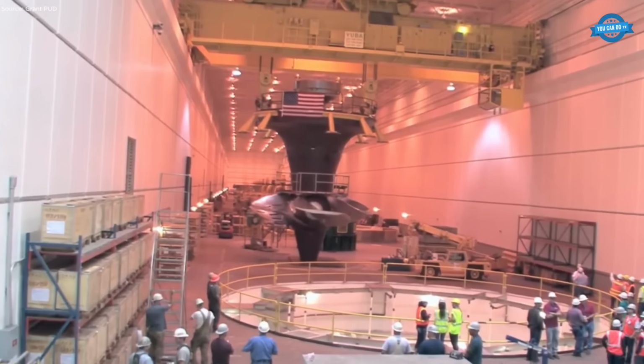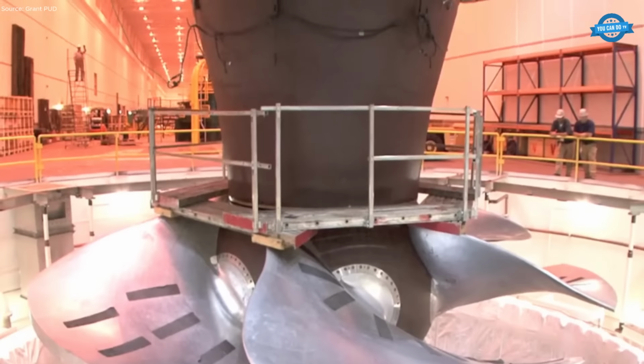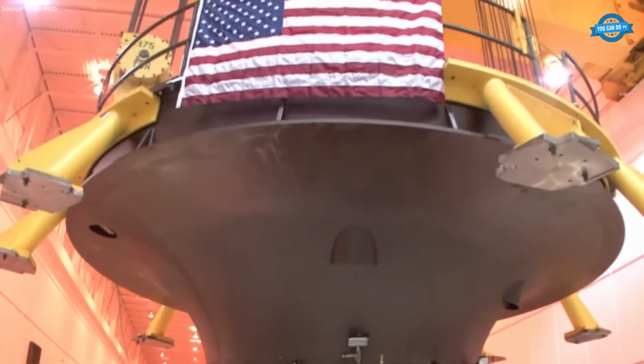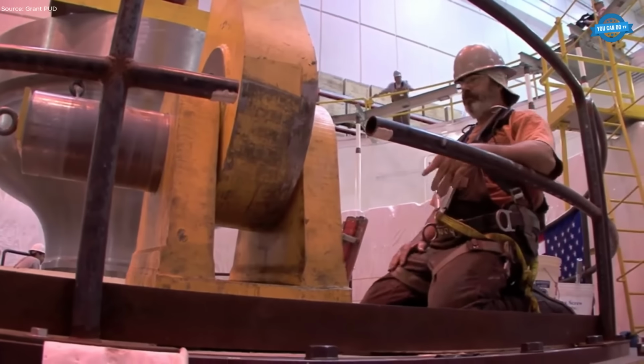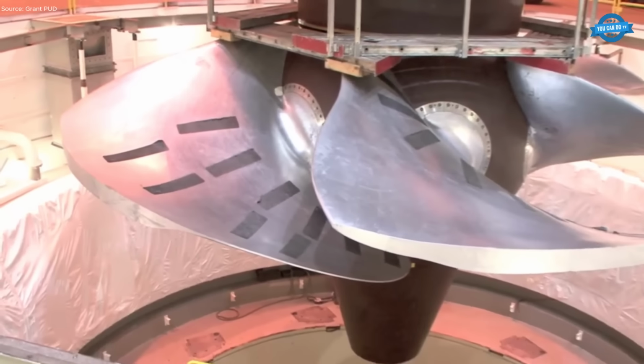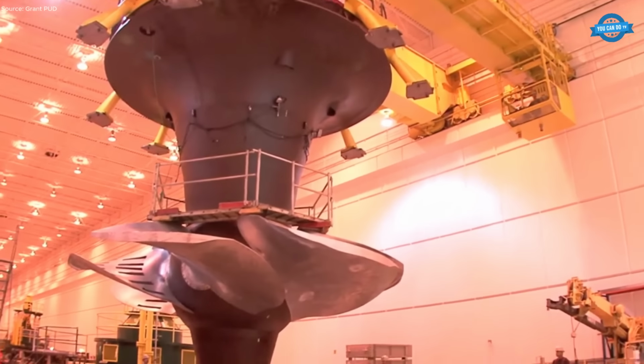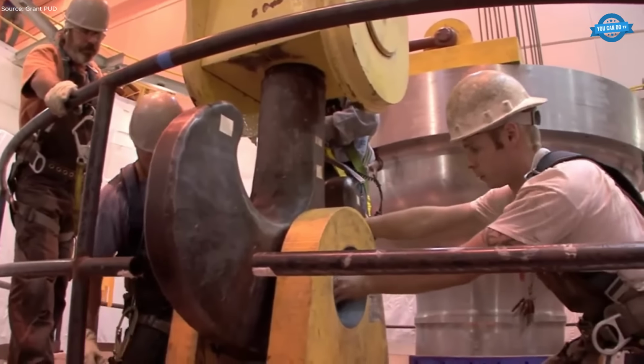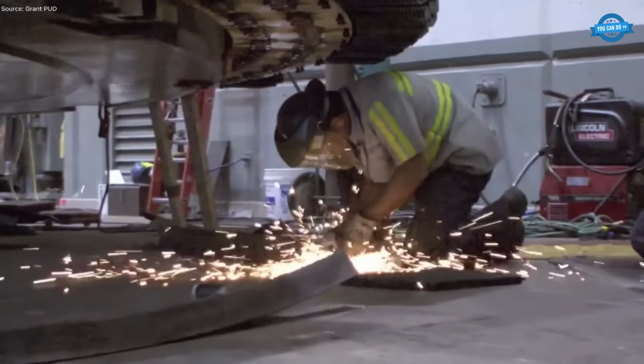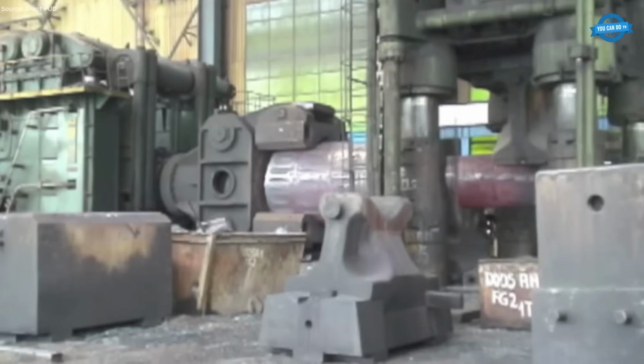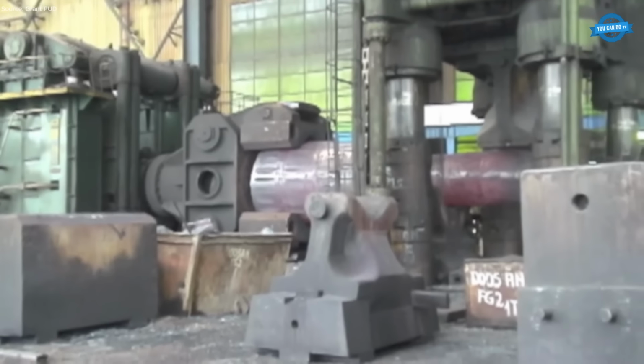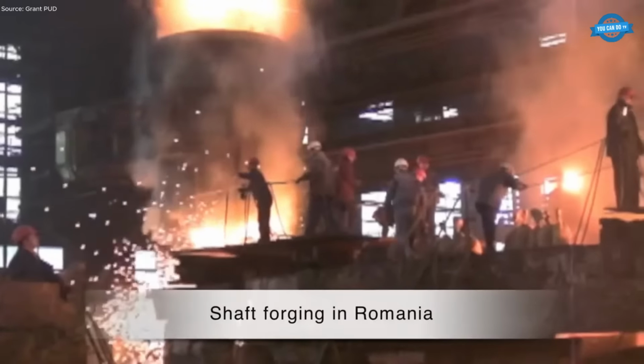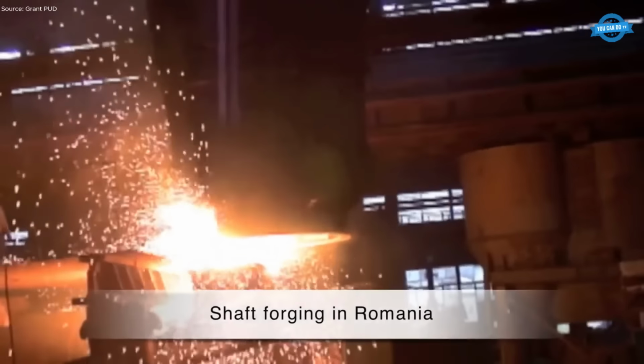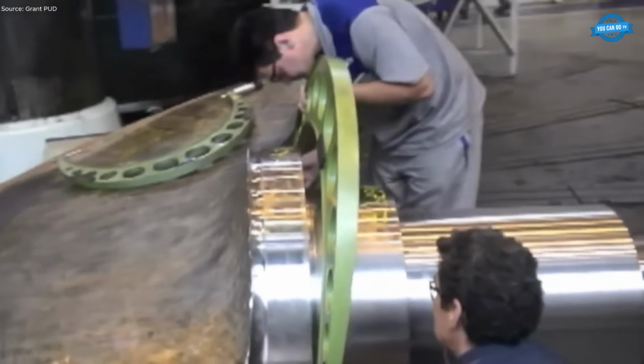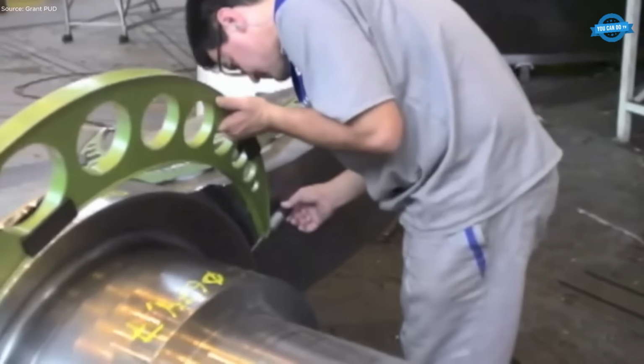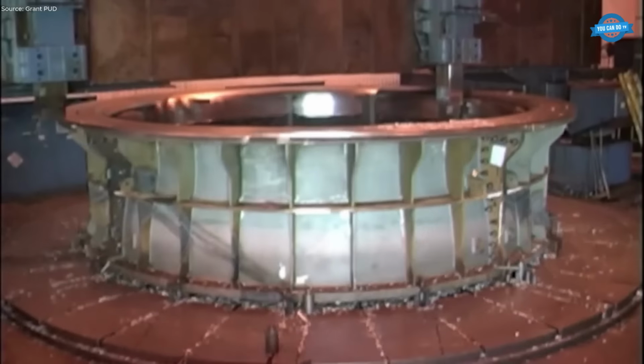At Wanapum Dam, engineers completed the final placement of the 10th turbine runner, head cover, and shaft assembly, marking the conclusion of a project that began in 2004. The new turbines, rated at 150,000 horsepower, replace older 120,000 horsepower units, delivering both higher output and efficiency gains of up to 5%. Precision inspections ensured components from suppliers worldwide fit seamlessly. Pre-assembly methods reduced installation time, while fish-friendly designs now combine efficiency with environmental responsibility.